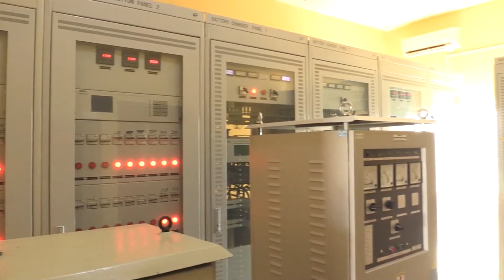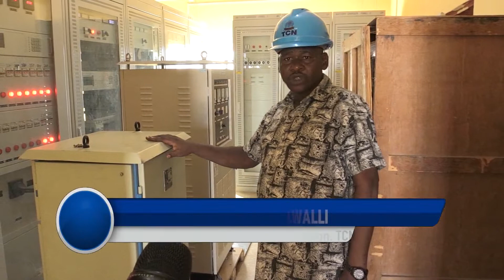In the substation's control room, the TCN official explained the role of the newly installed stabilizer. This equipment, a servo stabilizer, was installed to improve our DC voltage supply at the station. Initially we were having a low DC supply, but since installing it, the problem is over. We are now getting a correct DC output, and it helps in stabilizing the station.